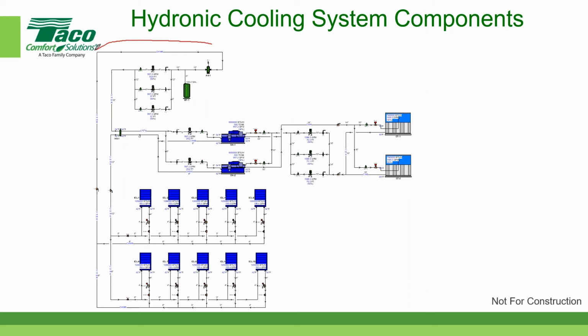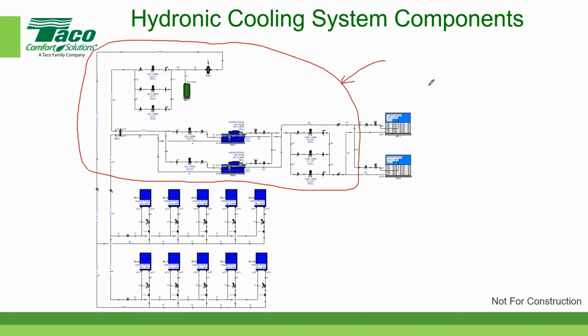And I actually have a slide where I'm going to focus and go into this in a little bit more detail. Kind of draw a line right up through here. There we go. So all of this stuff is inside the mechanical room. And I'll show you a little bit easier to read diagram. We'll dig into that. And then this equipment, these are open cell cooling towers because we're using water cooled chillers in this case. And I'll go over that in a few minutes. And those are outside the building exposed to the weather. So that's the stuff that's outside the building.